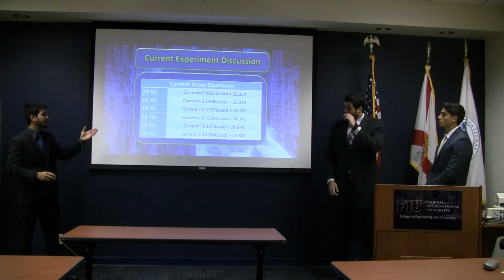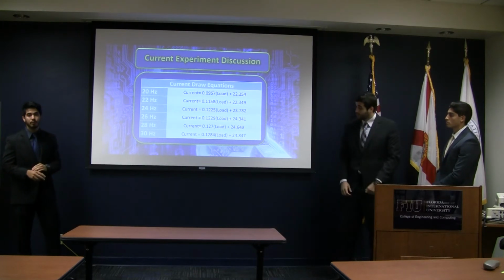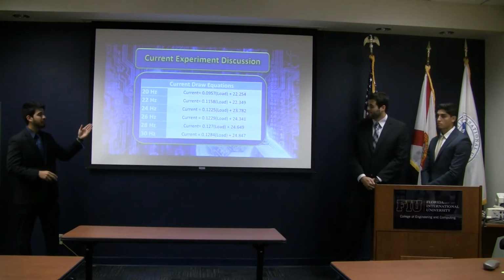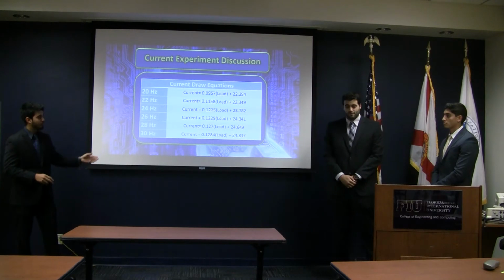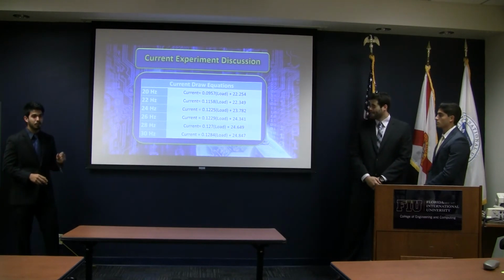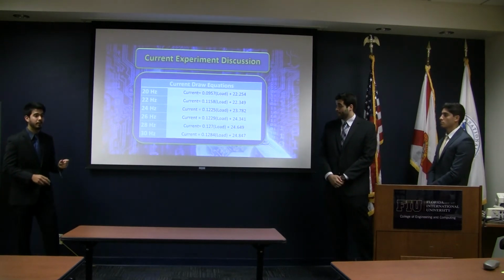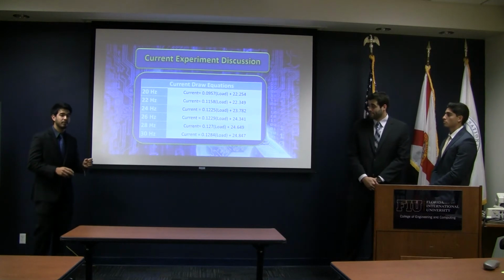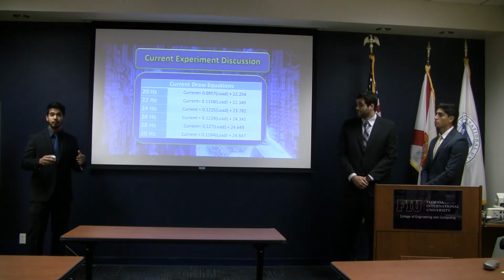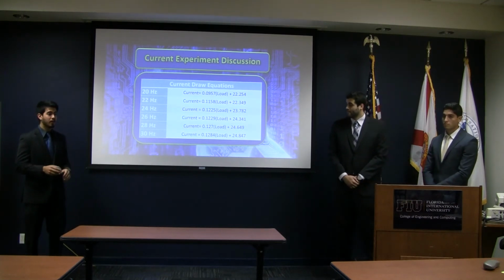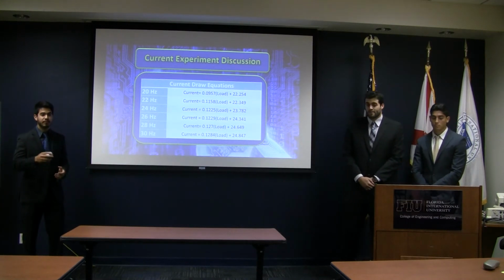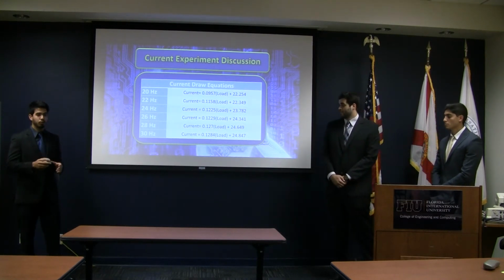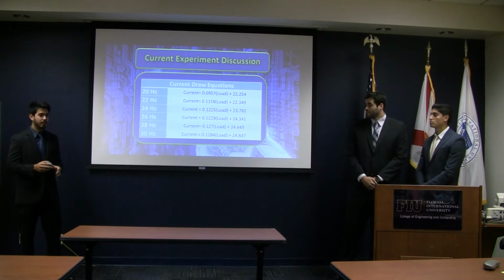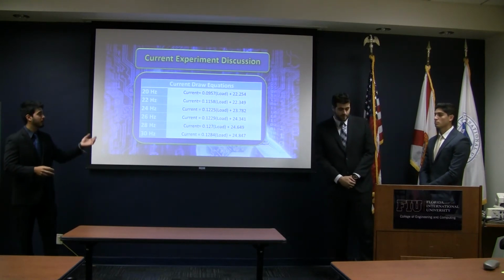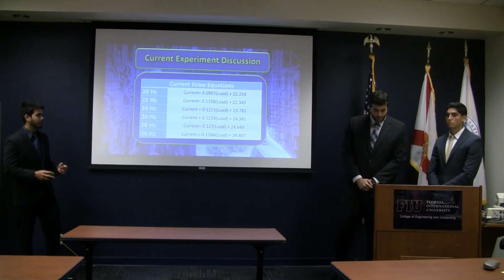These equations prove vital in the real world, because when our system catches an increase in current, since we have the relationship, we can calculate what increase in load was applied to the motor. Usually these load increases come as a surprise, because it could be internal resistance due to failure, or in HVAC plants, pumps building up residue that causes more resistance. This way we could calculate exactly what it is.